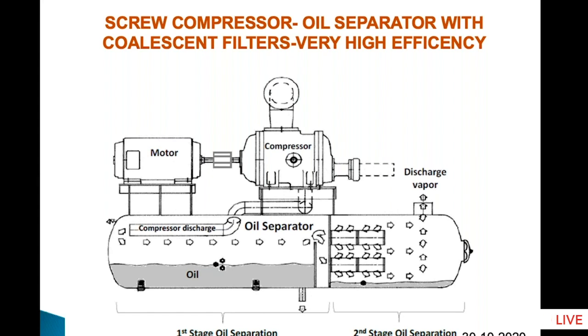If you look at this diagram, there is a two-stage oil separation. One is the compressor discharge, in which heavy density oil falls down. Then there is a baffle, and the remaining gas with low oil content goes through the coalescing filters. There are two filters, as you can see, through which the ammonia, oil, and gas travel, and most of the oil is recovered, and the discharge vapor is practically free of oil.